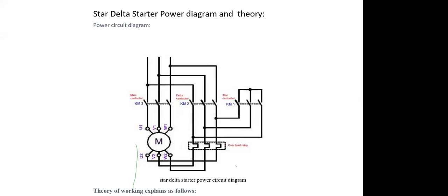If the line current is 100, my phase current is 100 by 1.732, and I will set the overload in phase current because, as we saw, it's a 6-terminal motor. So the line current is not going there. It is a phase current, it is going there.